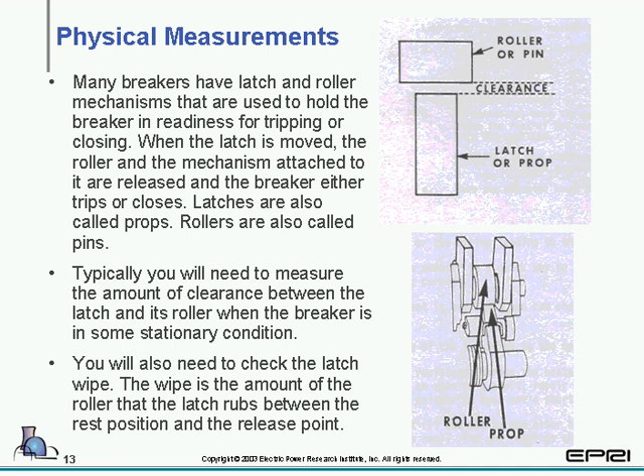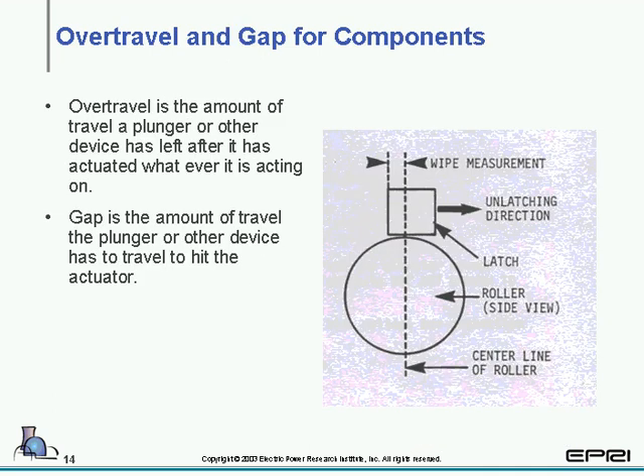Now, there's one other thing on all breakers and all designs as far as taking measurements that you're going to want to see, and that is over travel. Especially on your trip latches and your closing latches. Most of them have you set up and then back off until the breaker trips free or the latch cannot be set, and then to turn it in or set the latch or over travel to a certain degree. Very important when you do these two measurements, not only do you use the vendor's information, but common sense needs to be applied as well.